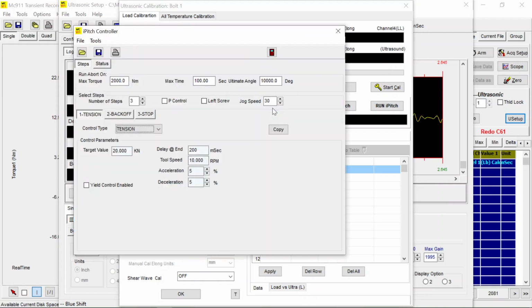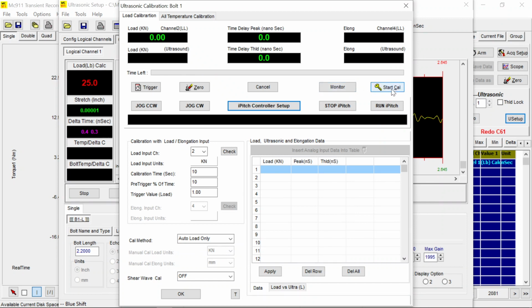Coming back here, we can look at the setup for the iPitch. We can control on tension, control on tension. Let's say it goes up to 20 kilonewton with 10 RPM. And then let's just back off at the end and stop. Same control that we had before. And let's say back off around 360 degrees. So that's our control strategy. We're ready to go. We can click Start first and zero the ultrasonic signal and make sure this is close to 0 also. Then we have already done our setup. We can run the iPitch.